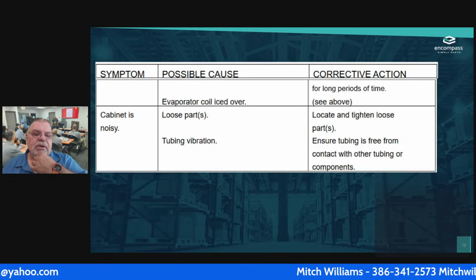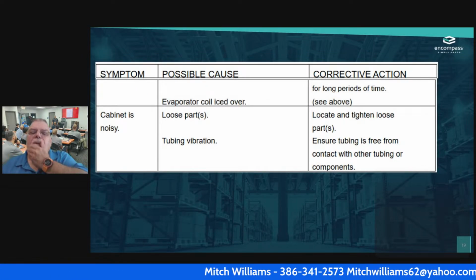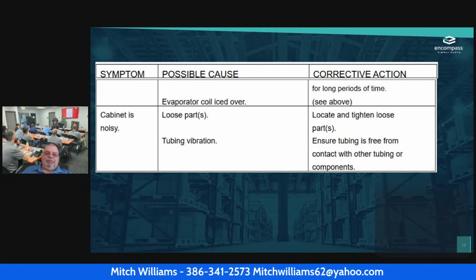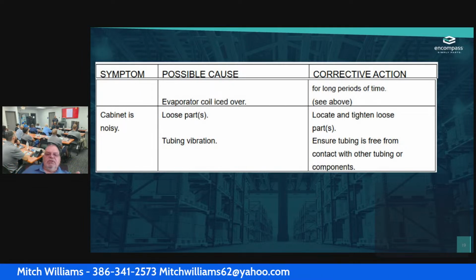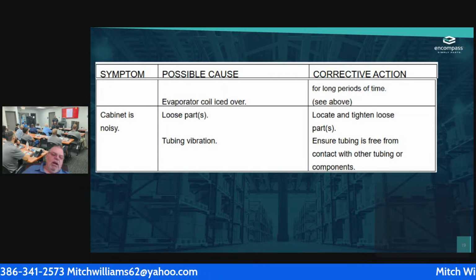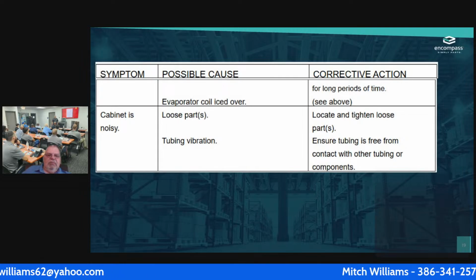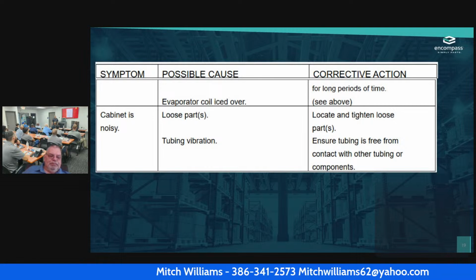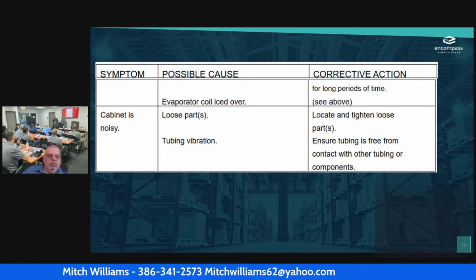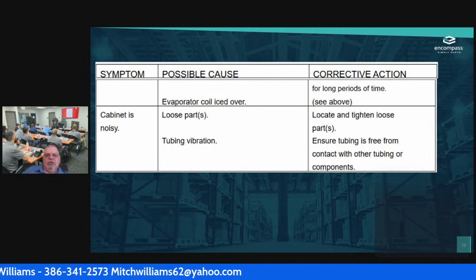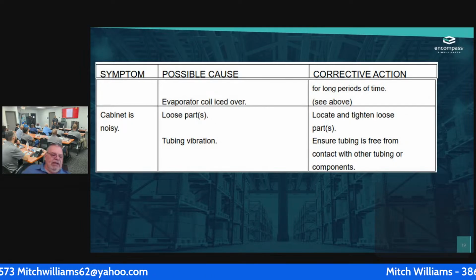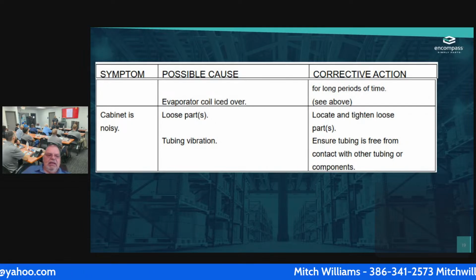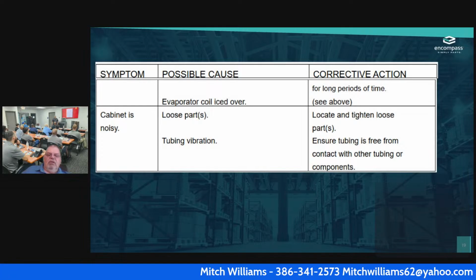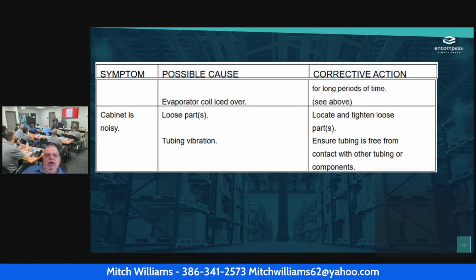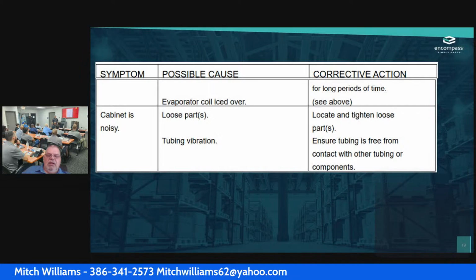Okay. The cabinet is noisy. I'm sorry, I skipped one. The evaporator coil is all iced over. So what I'm going to have to do is go in and see what the coil is set at. If it's set too low, then I have to raise the temperature a little bit. I need to find out, once again, that nobody has overloaded it. I have to make sure that somebody hasn't been in it all the time.